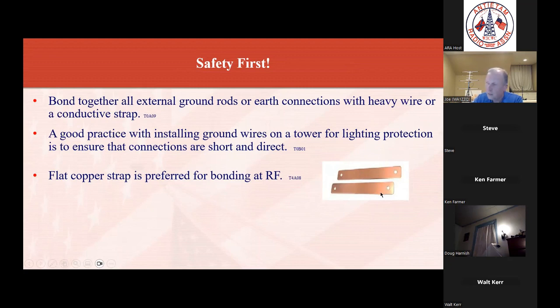As a matter of interest, for the same amount of metal, a flat strap will have a lower resistance than a round wire. You can work that out, you calculate it. But the operative factor here is the surface area. That's why flat straps work better than round conductors. Excellent point, thanks Steve.